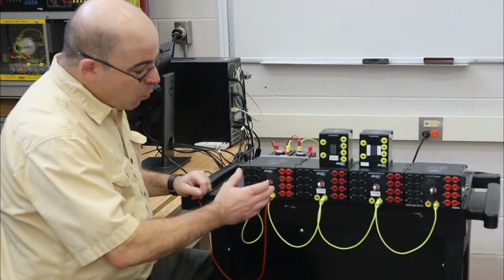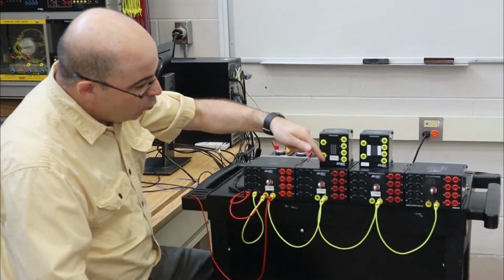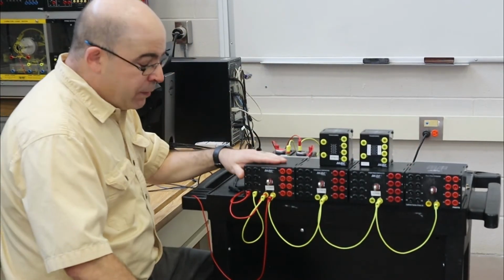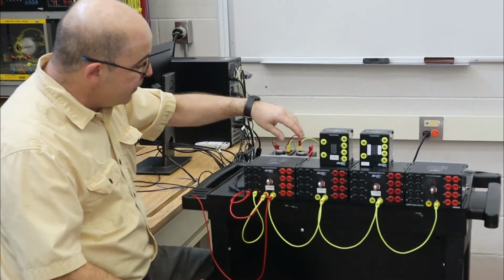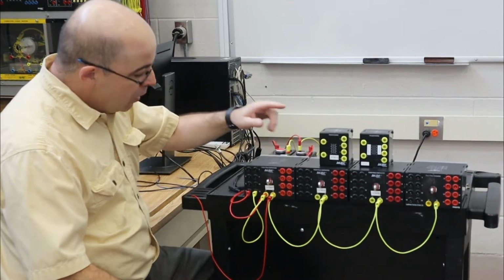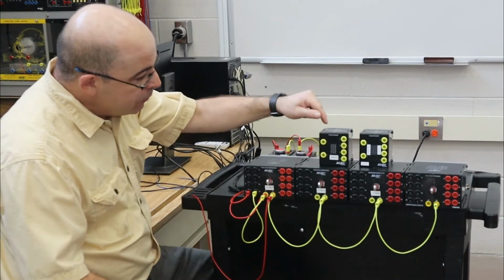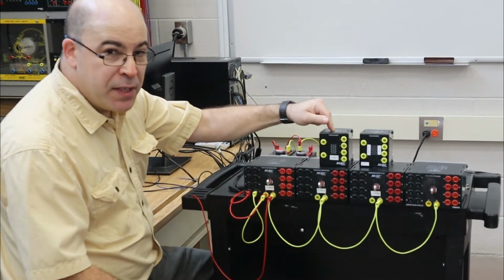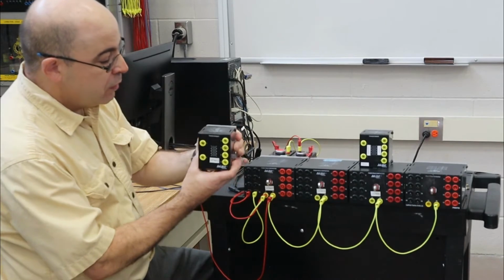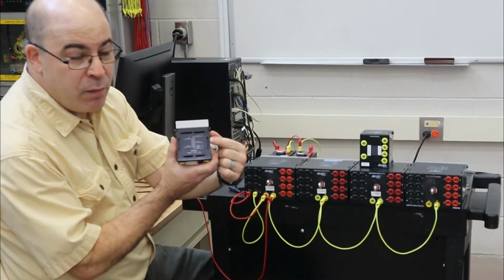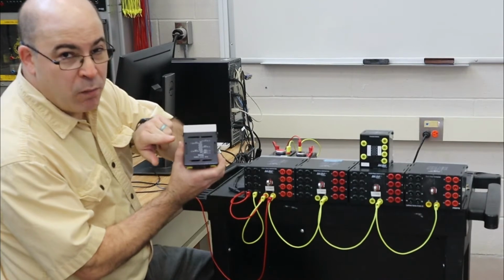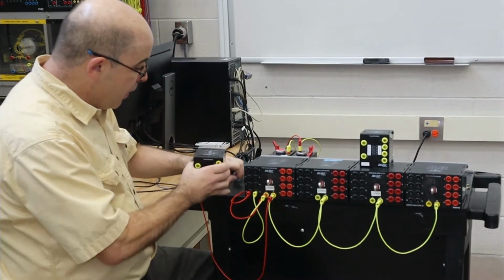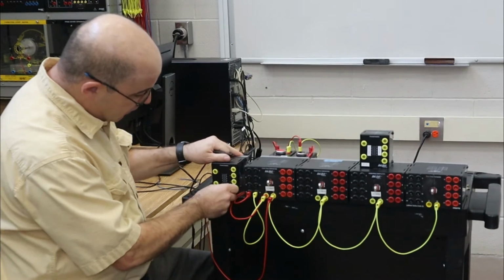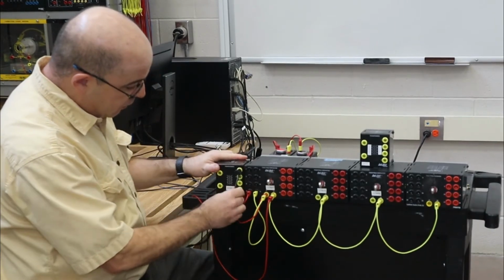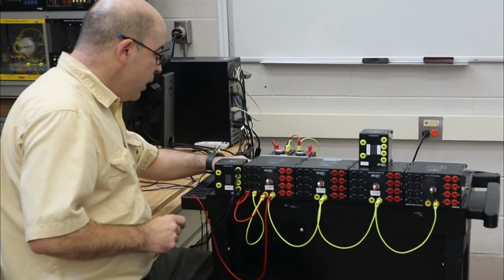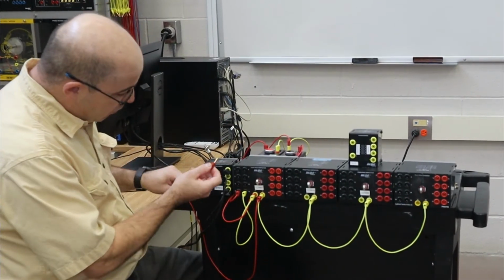So here we are. What I've done is I've assembled a series of 4 individual relays. My goal here is we're going to build a simple control circuit with a holding contact, and I'm going to start off with the 25 VA transformer. Now, this transformer has an input of 208 volts and an output or a secondary of 120 for the control circuit. So I'm going to go ahead, wire up for the 208 on the primary, and then we're going to power it up.